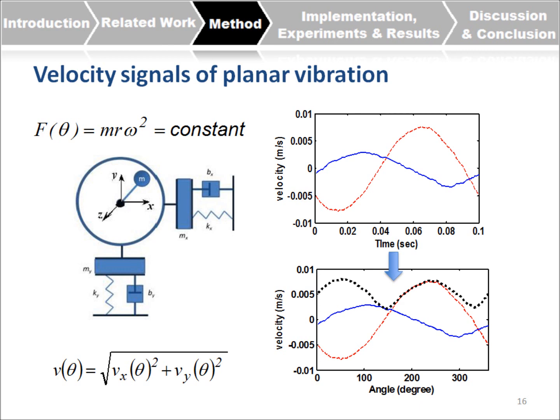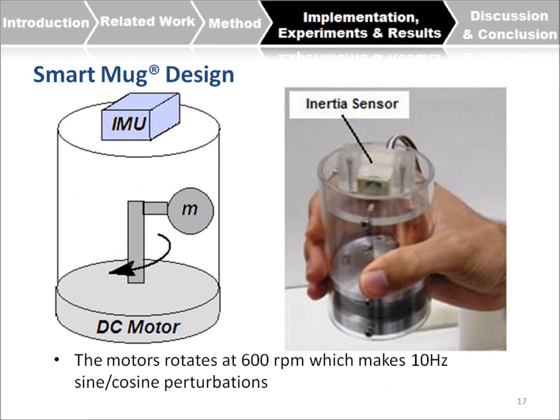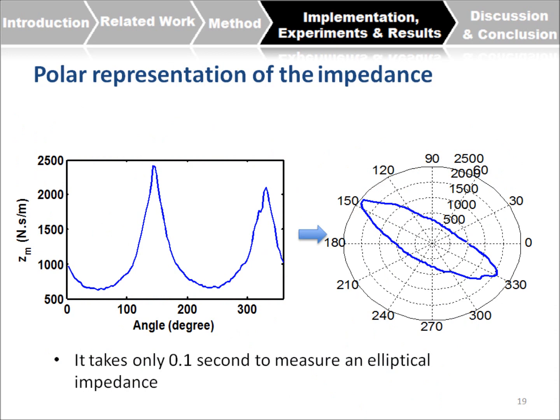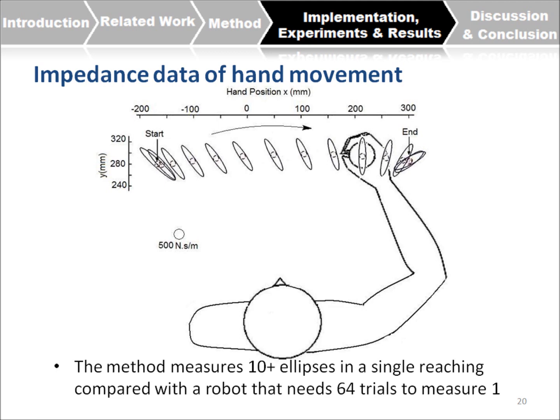The device design uses a DC motor that rotates a mass and an IMU sensor that measures the response to the perturbation. The rotation frequency is 600 RPM, which is 10 Hz, so the mass rotates 10 times per second. Taking the acceleration signal, integrating it, and transferring it to angle space, then combining X and Y velocities, we use the equation dividing force by velocity to get impedance in every direction. Plotting impedance in every direction on a polar diagram reveals the major and minor axes expected from robotic measurements.